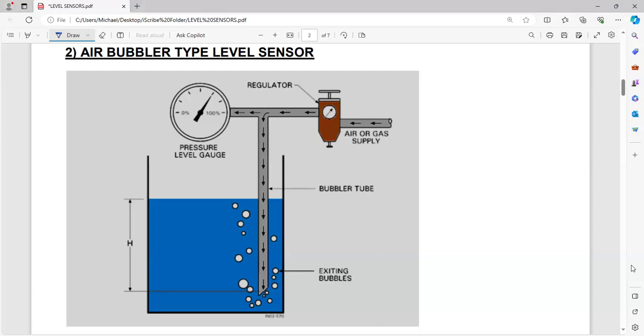Okay. Now this air bubbler system level sensor has a very simple arrangement, a T arrangement, as you can see. Here you will have a 7 kg per centimeter squared normal engine room pressure that is coming here to a regulator, and this regulator will ensure it might be slightly higher than this 7 kg. It is adjusted such that when the tank is empty, all the air will be coming out into the empty tank.